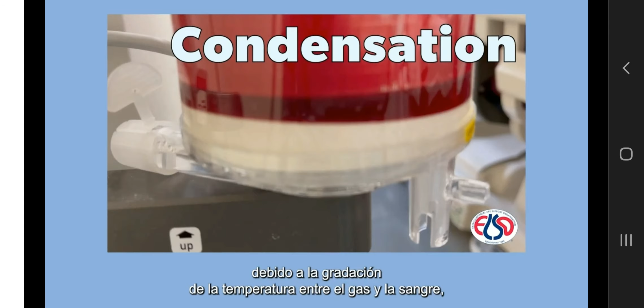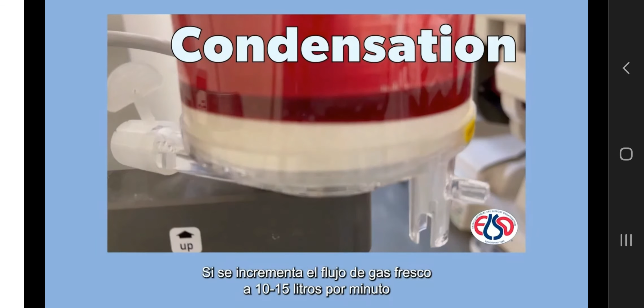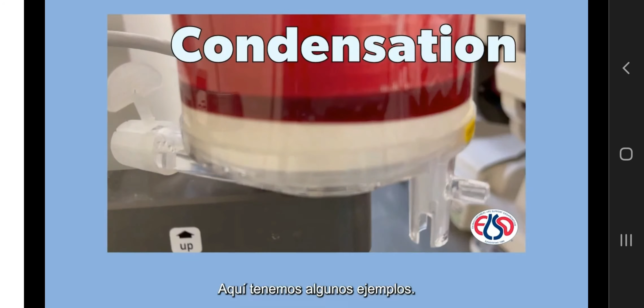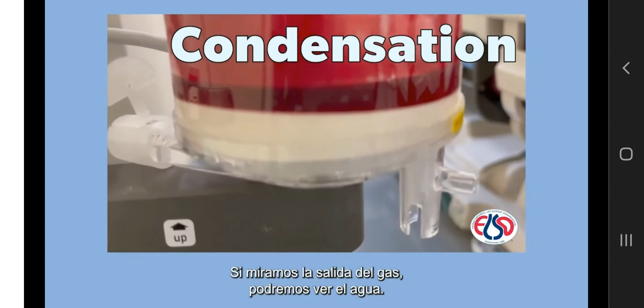Apart from thrombosis, condensation inside the hollow fibers, the gas compartment, due to the temperature gradient between the gas and the blood, the so-called wet membrane, may impair carbon dioxide removal. Increasing fresh gas flow to 10 to 15 liters per minute in the adult patient with polymethylpentene membranes for a few seconds may purge this water. We have a couple of examples here. Look at the gas outlet. You could see the water.